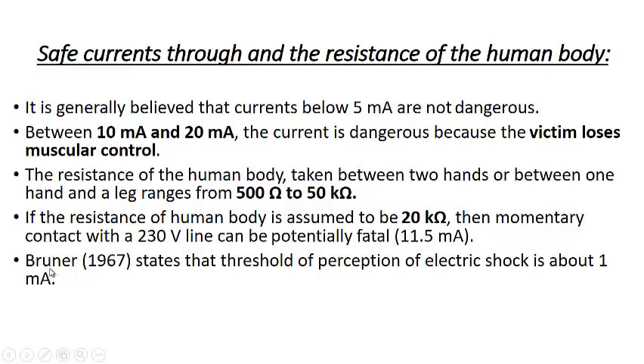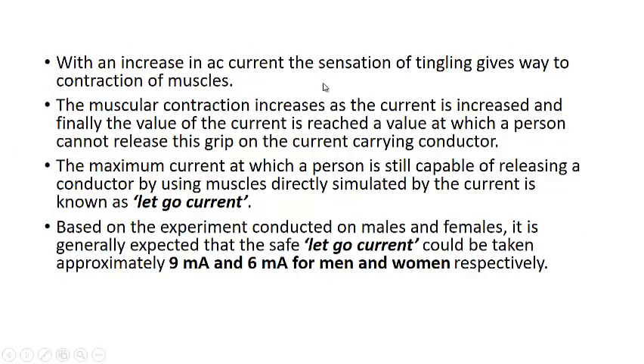Usually, Bruner states that the threshold of perception of electrical shock is about 1 milliampere. As I told you, 5 milliampere is not dangerous, but you can perceive the electric shock if the current flowing through your body is 1 milliampere. With an increase in AC current, the sensation of tingling gives way to contraction of muscles. The muscular contraction increases as the current increases, and finally the current reaches a value at which the person cannot release the grip on the current-carrying conductor. Beyond that threshold value, a person will not be able to release the grip of the conductor.